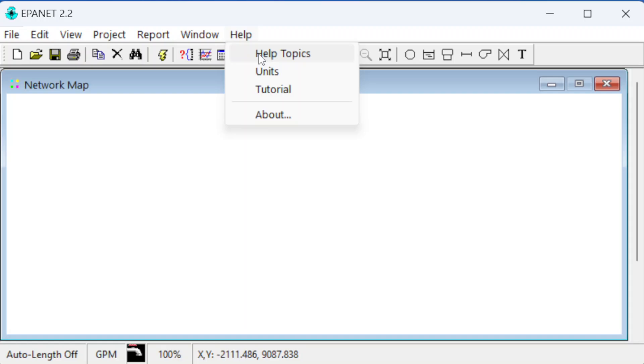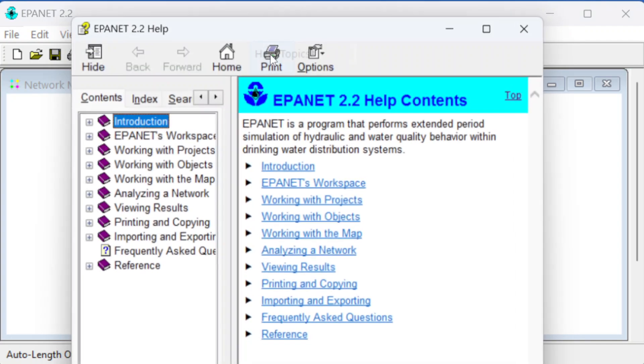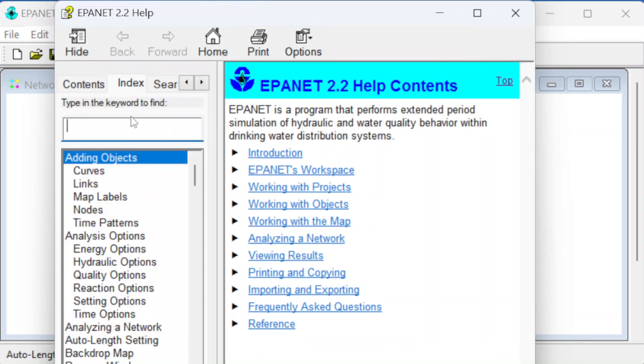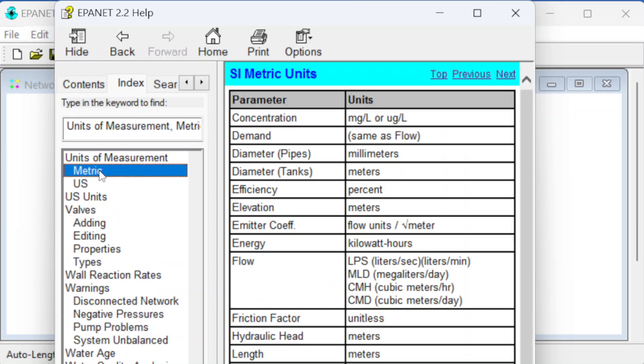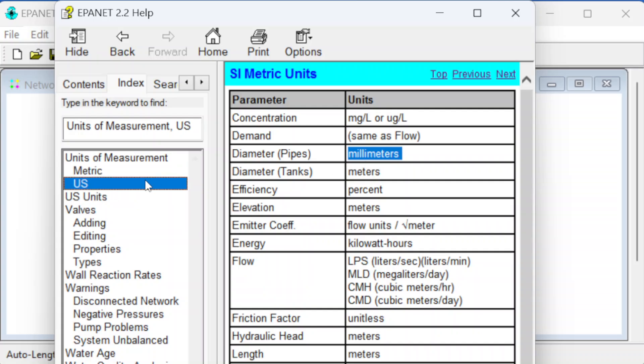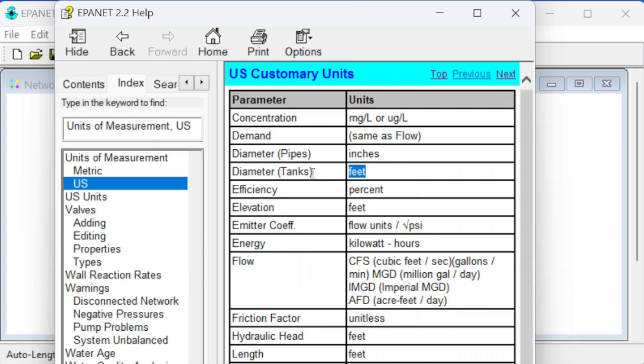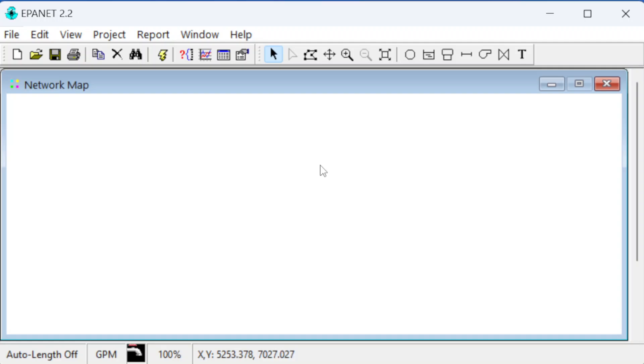You can pull up the help file — the one online is a little better, but there is one here. Under Help Topics you can look up units of measurement. For metric, demands are in the same units as flow and diameters are in millimeters. In US units, tank diameters are in feet and pipe diameters are in inches. You have to check this because the software doesn't show you the units when you enter data, so it's good to keep that in mind.